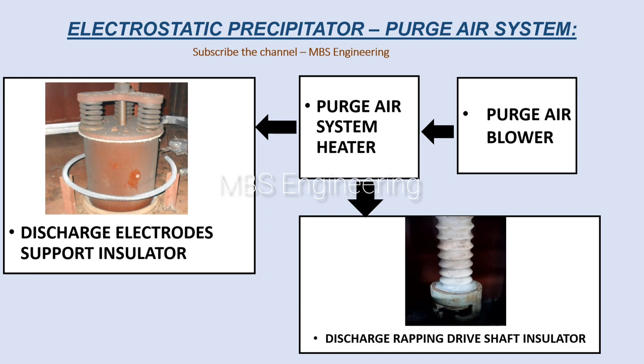Please refer to the ESP purge air system block diagram and working layout for better understanding. Step one: the purge air system is a combination of heaters and air blowers. Step two: it provides hot air to preheat insulator compartments and preheat the discharge drive shaft insulator. Step three: the system generates high temperature air to insulator compartments and maintains positive pressure inside them, preventing dust from going up through the HV insulators. Step four: this system assists in reducing localized sparking, moistness level, and corrosion factors in the ESP's internal parts.